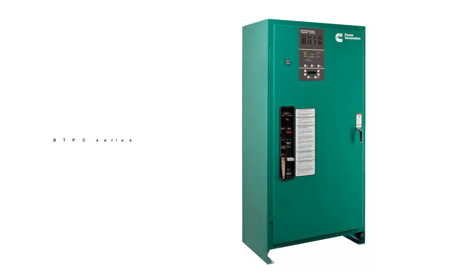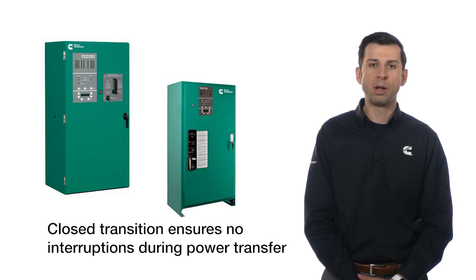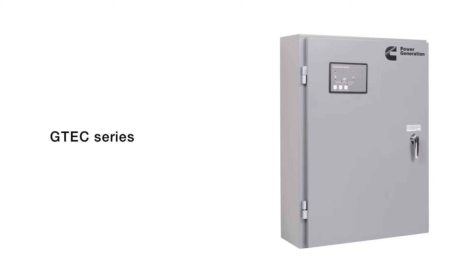Also designed for this market is our bypass transfer switch, or BTPC, which provides redundant power transfer when the ATS needs inspection and maintenance. This series offers more advanced controls with more sophisticated sensing and metering. Closed transition is also available on the CHPC and BTPC to ensure no interruption during power transfer. Overall, this product line offers maximum reliability for critical applications.